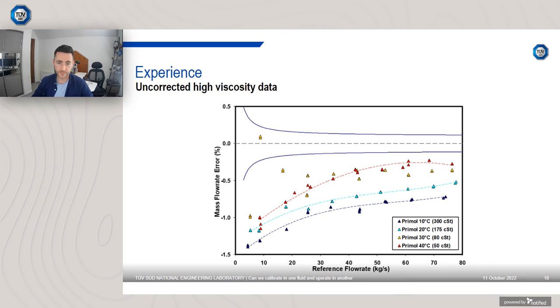So what you've got here is potentially two effects, temperature and viscosity. However, this is the same meter as before. We've seen that there wasn't a significant temperature effect, so we can almost solely attribute the effects here to viscosity for this meter, for this calibration. Again, got the same y-axis scaling, kept it consistent with the previous just to show you the deviations, so 0.5 to minus 1.5. Still reference flow rate, and you can see here we've got a clear trend with viscosity.